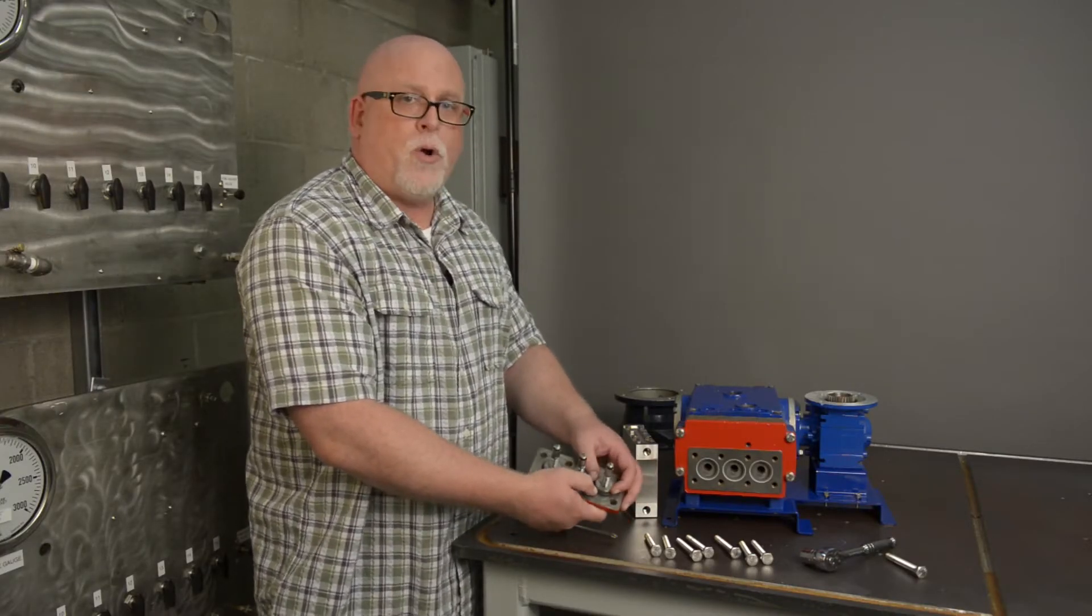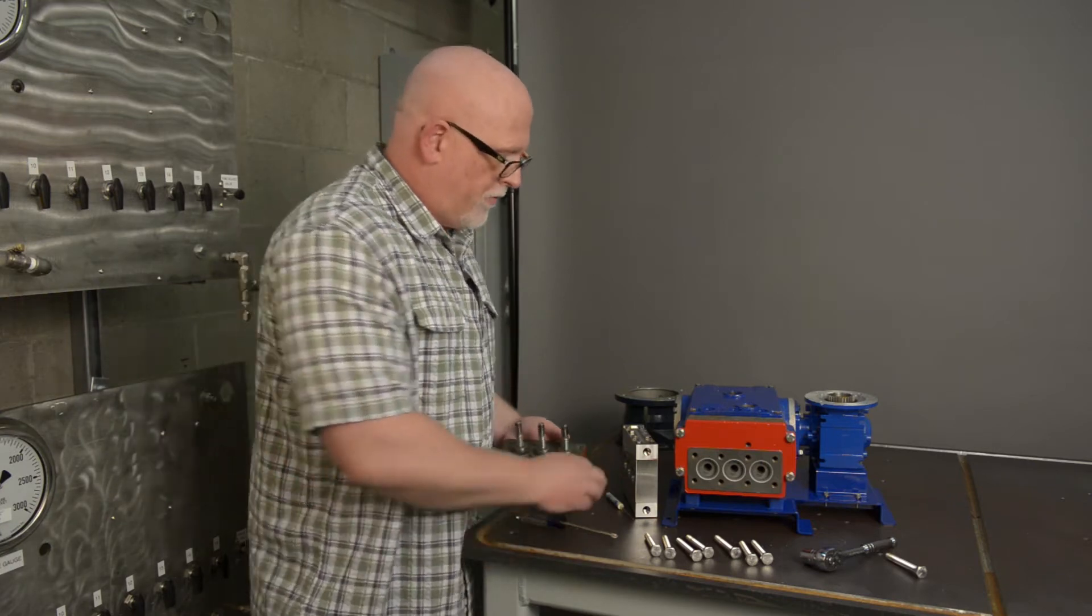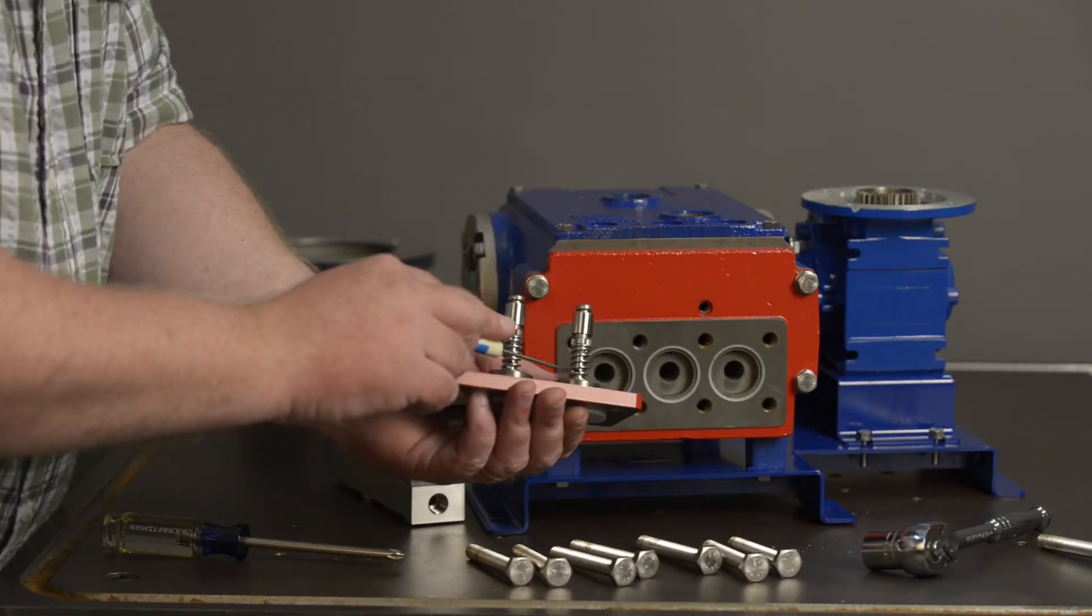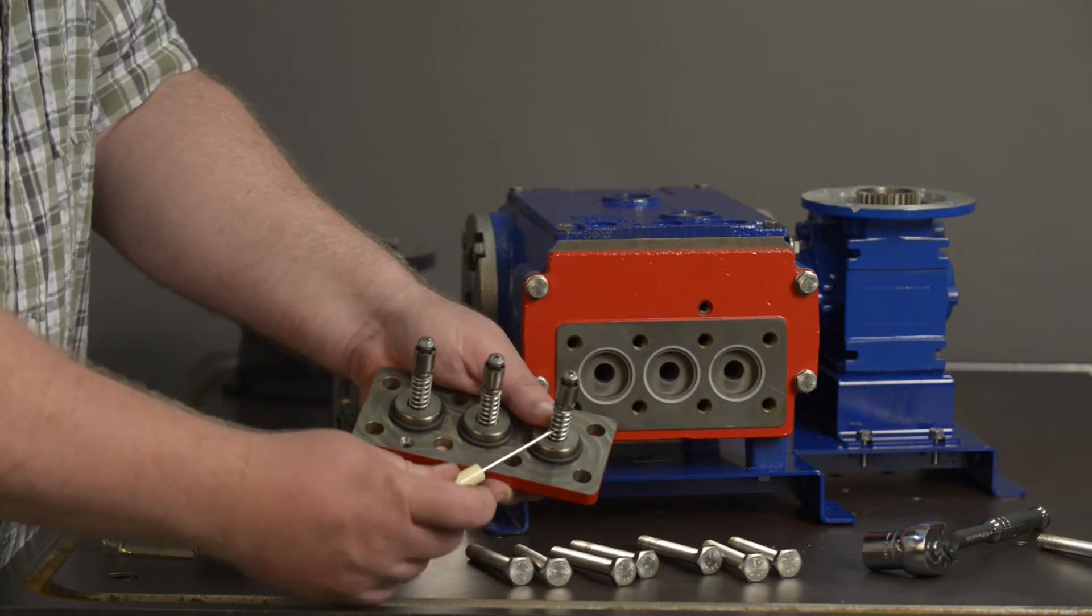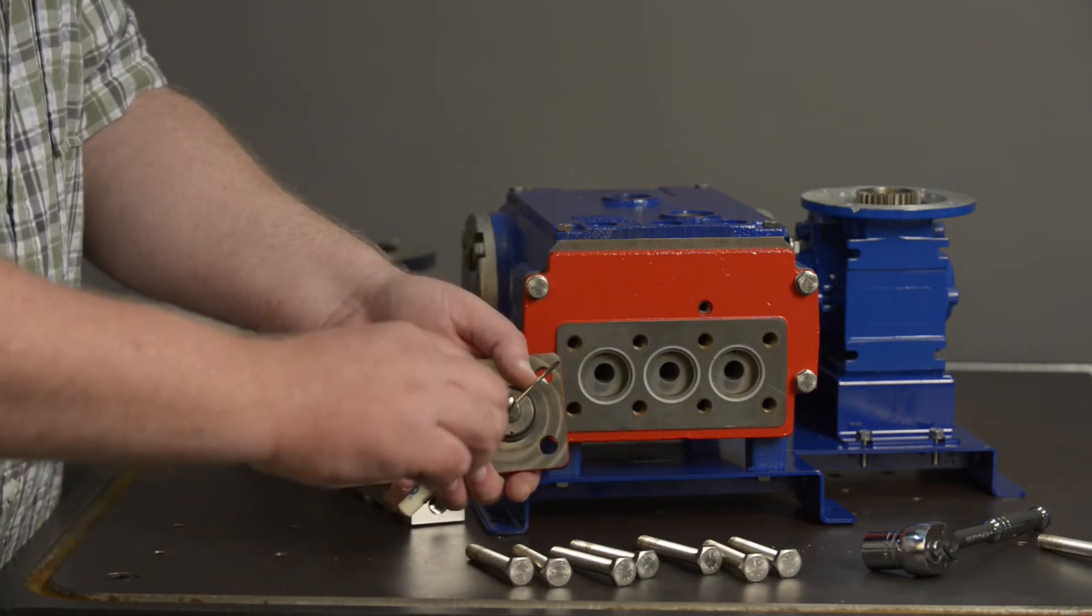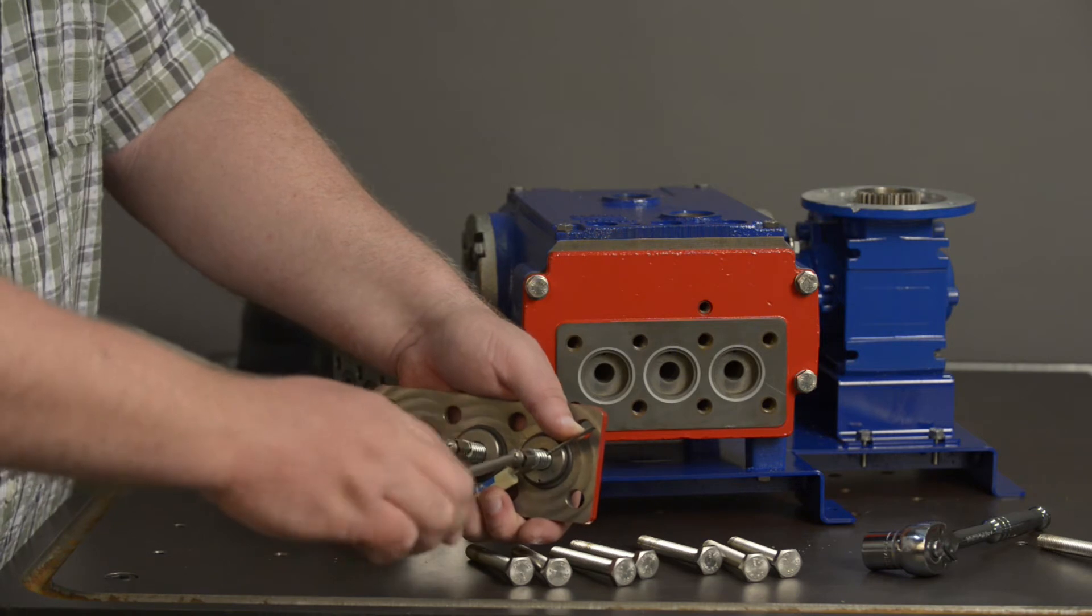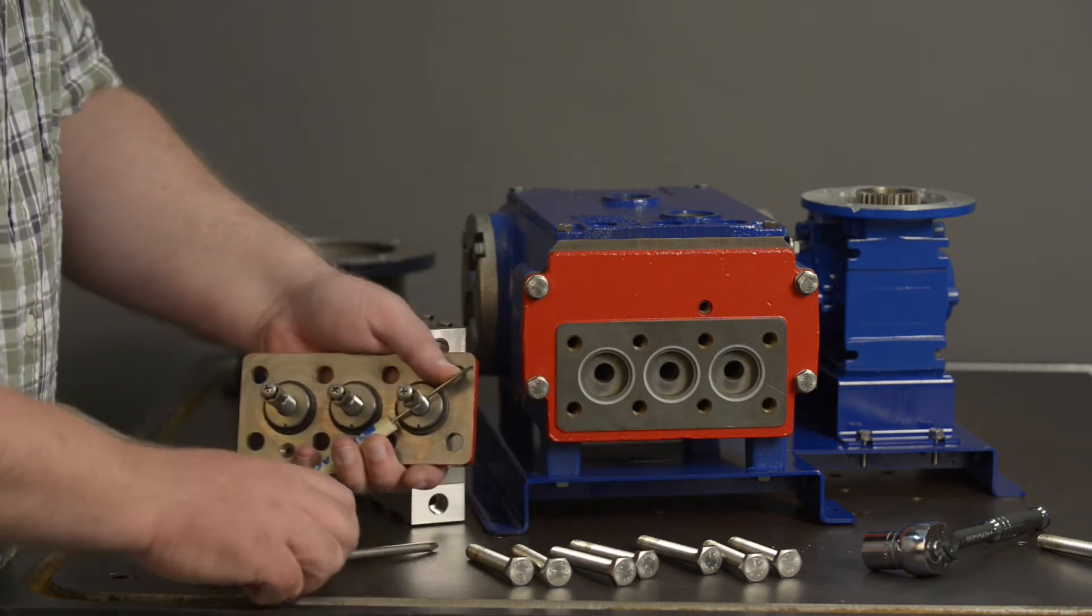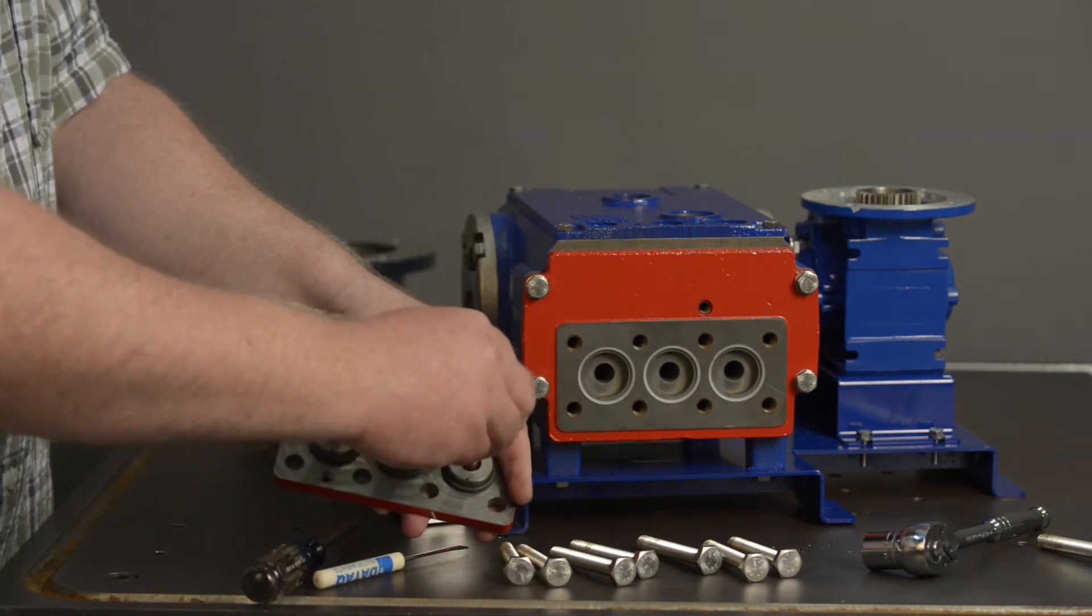Now to remove the diaphragm, that's where your small screwdriver or Allen wrench comes into play. You'll notice on your diaphragm spool valve assembly, there's a small hole in the plunger. Push your screwdriver through that so it comes all the way through. Take out your Phillips screwdriver and these are just snug, and you unscrew them. Remove the screw all the way. Remove the small screwdriver from the spring and that all pops out just as one assembly.